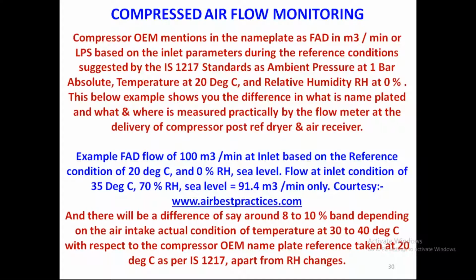As I was telling you before on the blower, air at 20 degrees has a density of 1.22 to be precise, whereas the density of air at 45 degrees is 1.09. Straight away you get a 10% difference, because all the meters we are using are mass flow meters. So wherever the density changes are there, at 30 to 40 degrees, that is why we always suggest to the industry to reduce the compressor house temperature so that it is on par with the ambient surroundings.